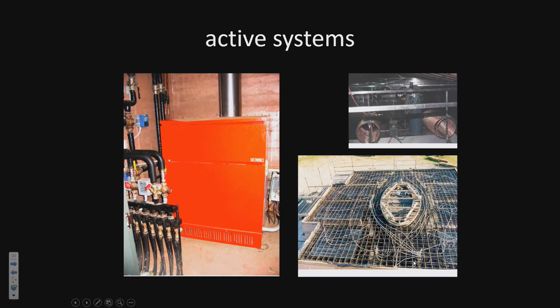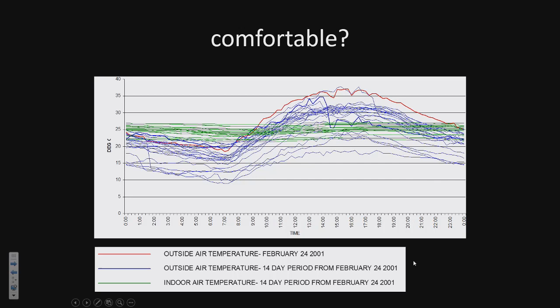And how does it perform? These are some monitored results we got off the system in the first summer after it was opened, when the cooling ceiling was not commissioned yet. So this is the building operating simply with the night cooling. You can see the temperatures hitting -- the green is the building, the red and blue are the outdoor temperatures. They're hitting over 35 degrees and consistently over 30 in the daytime, dipping down to typically about 15, but as much as 10 at night. So that's that sort of desert climate condition that really helps us with the thermal mass. But the building stays stable.